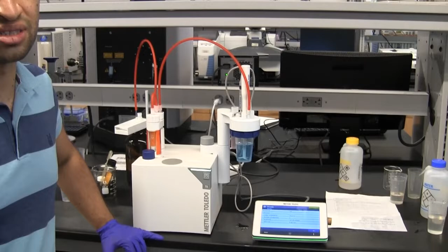So we redid the calibration with actually the same pH buffers without changing them. This time they are better, the values are better. And also the slope cal, as we said, is between minus 55 and minus 59. And the 0 cal is between 6.8 and 7.2. So click OK, and we'll go and check the results.